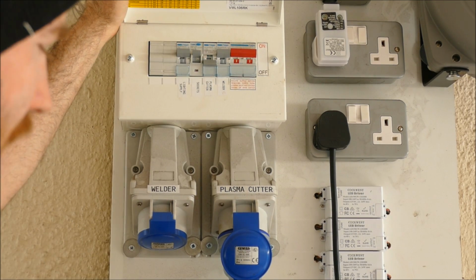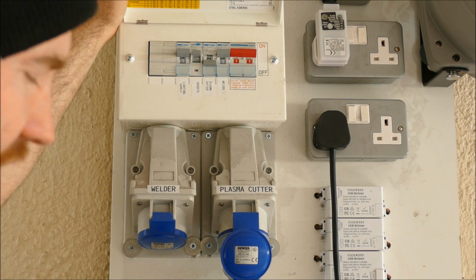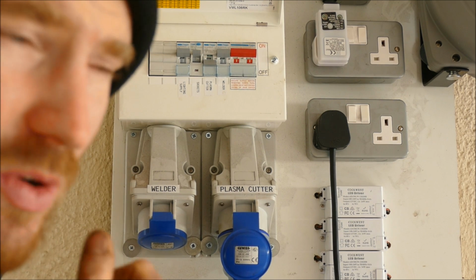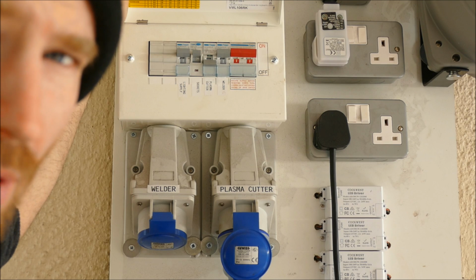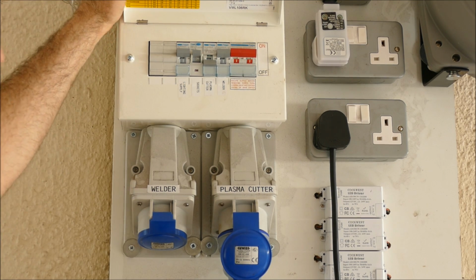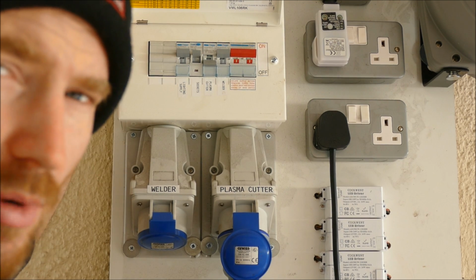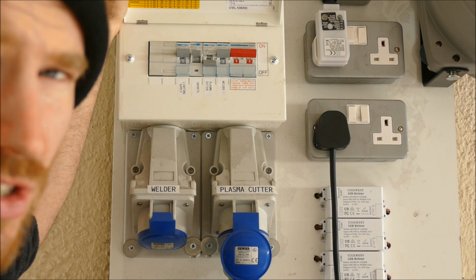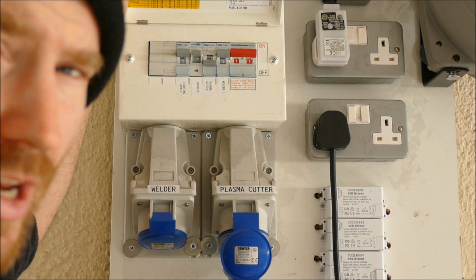What I've got it hooked into is a 32 amp plug with a corresponding 32 amp breaker. It's recommended that you use a 10mm wire, but I've used 6mm and that's rated up to 42 amps, so I believe I'm within the safe zone. Just so you know, I'm on a domestic supply, and the fuse going in is rated at 100 amps.